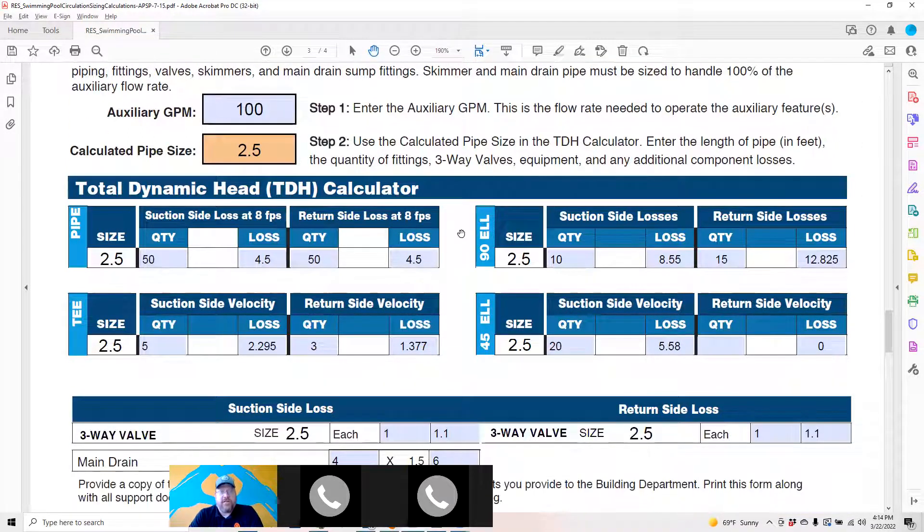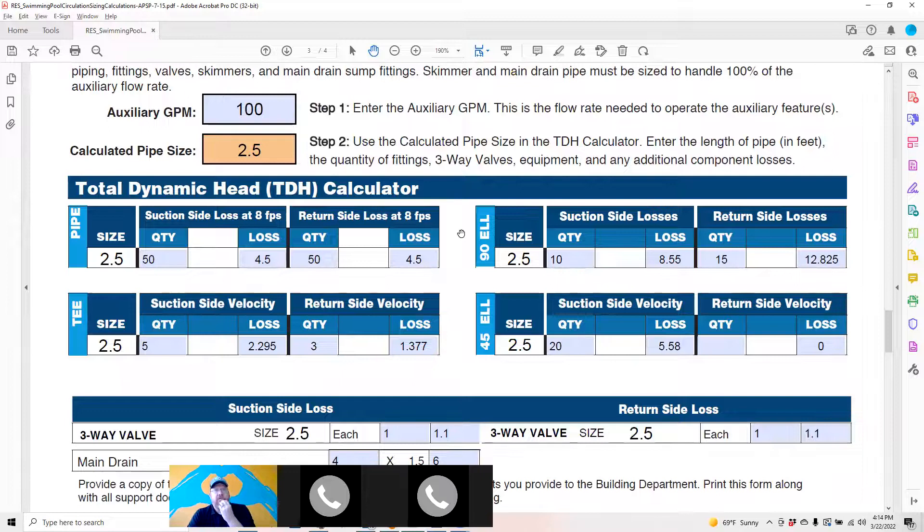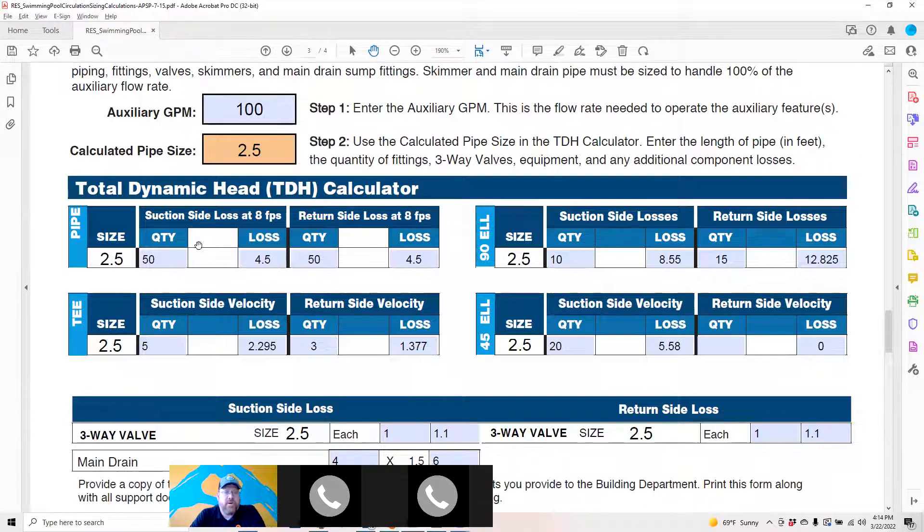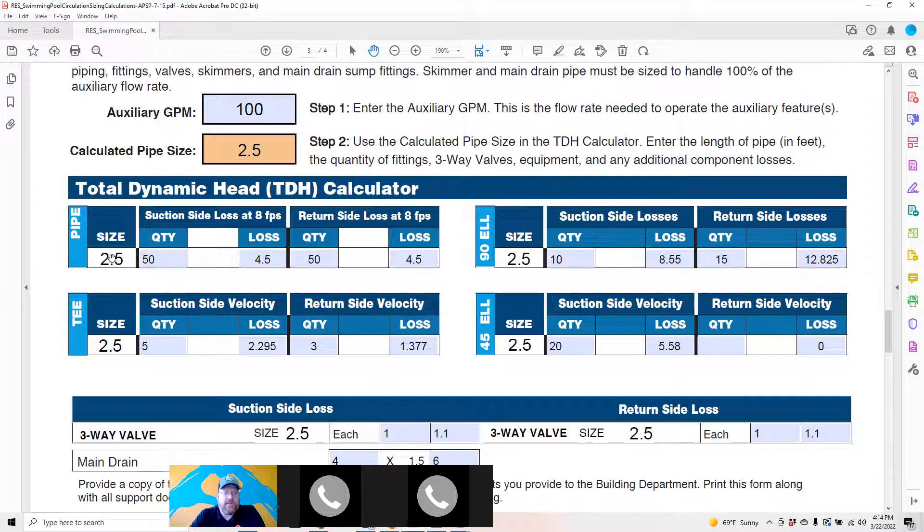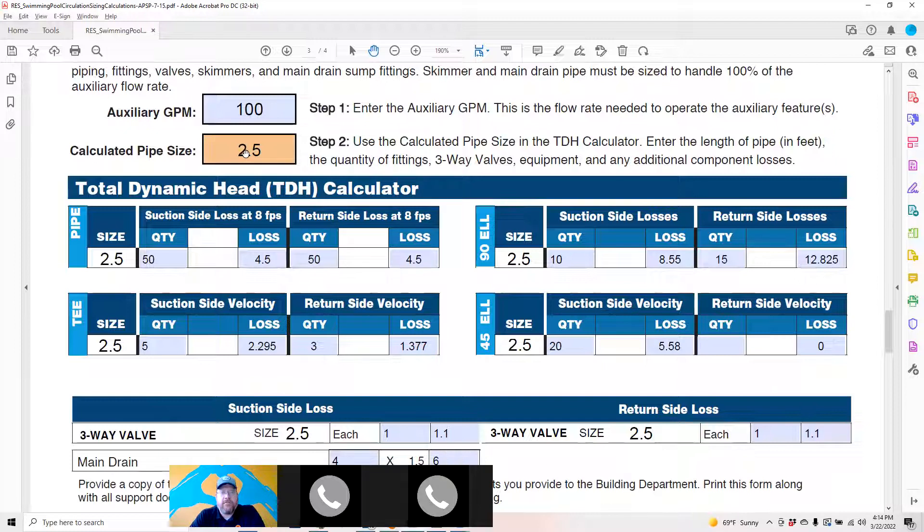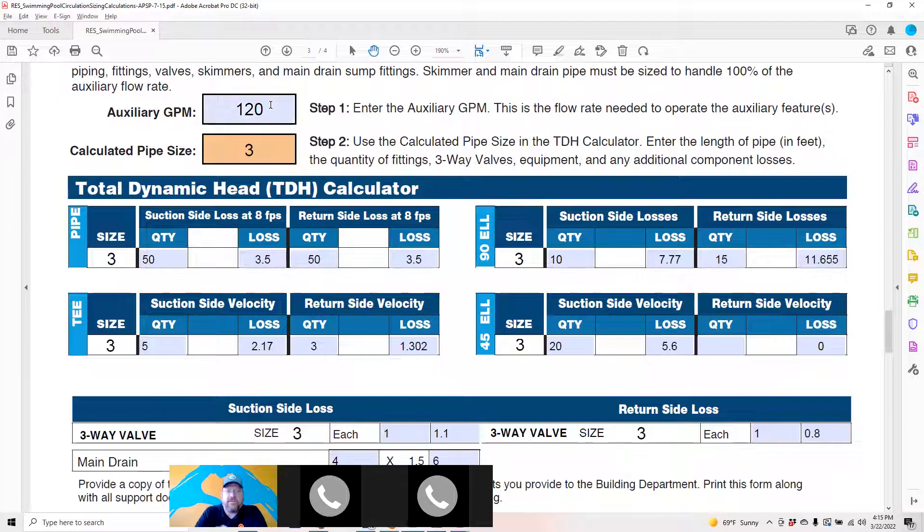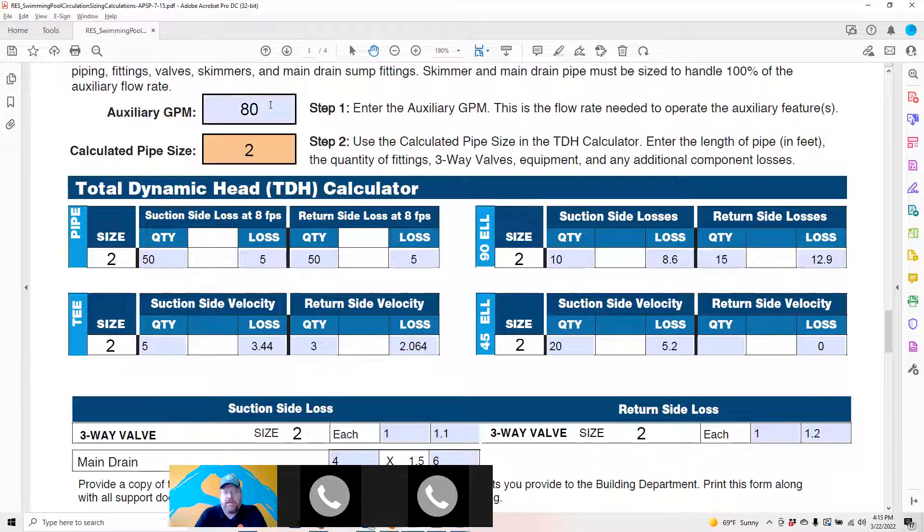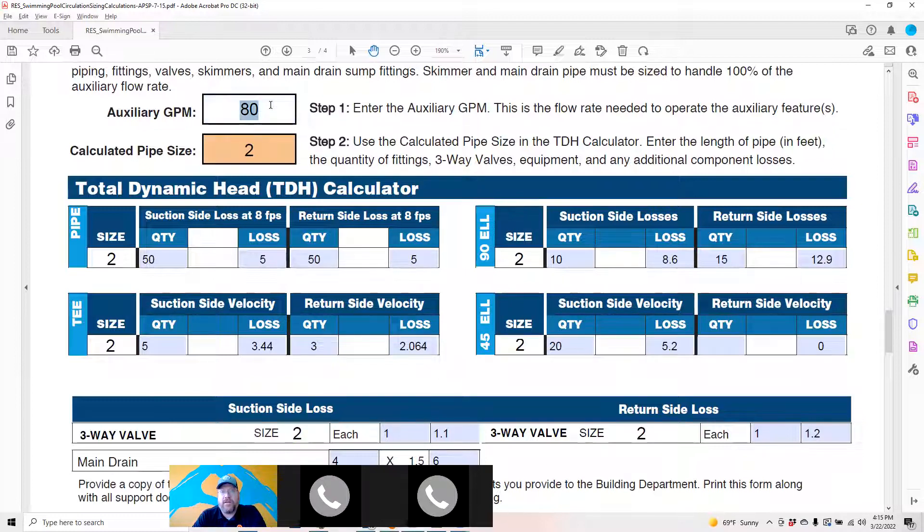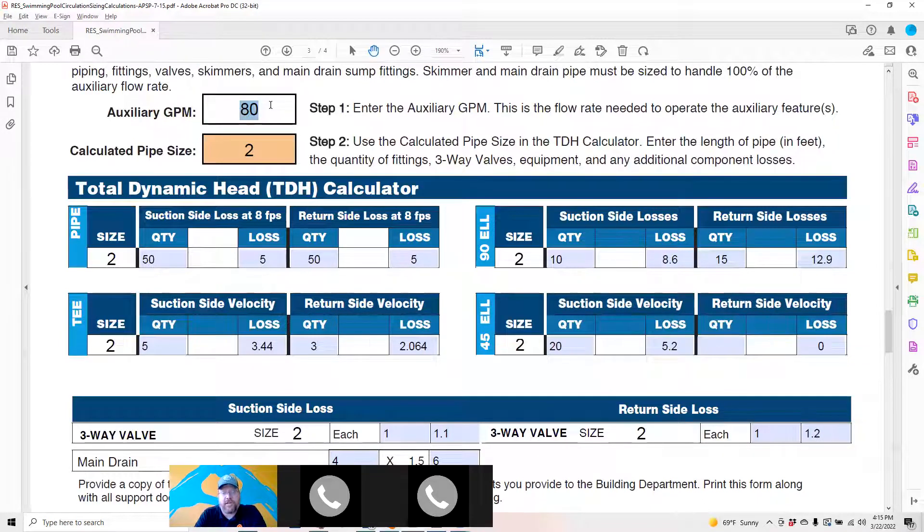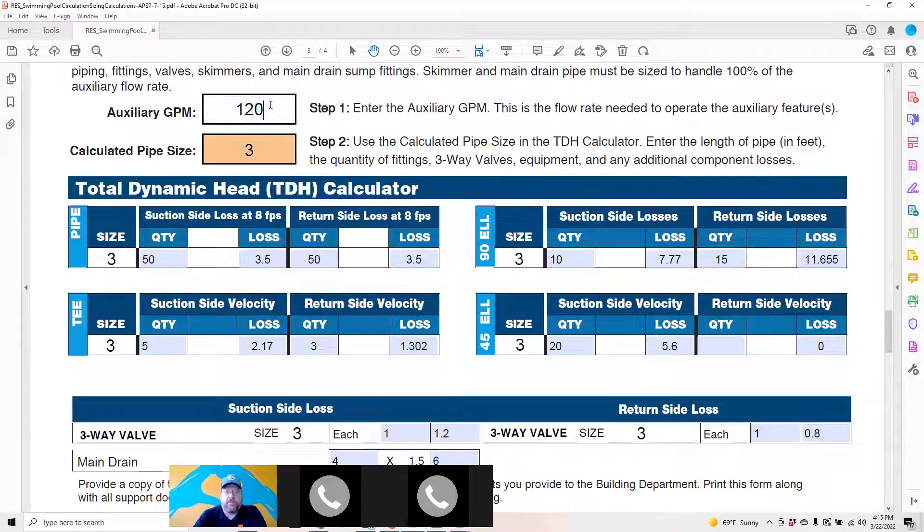Page three is a hot mess. If you're using it to calculate your TDH, you're in for an adventure because there's no way to change this pipe size or this pipe size from this particular setup. In order to change the pipe size, you have to change this auxiliary GPM. At 120 it gets to three, at 100 it'll calculate for two and a half, at 80 it'll calculate for two.